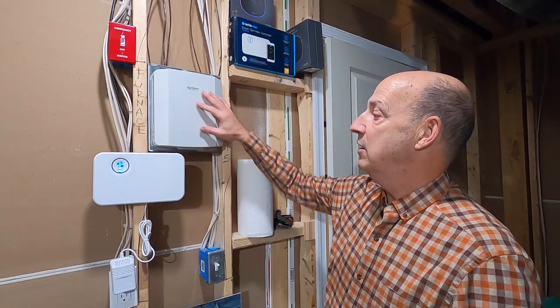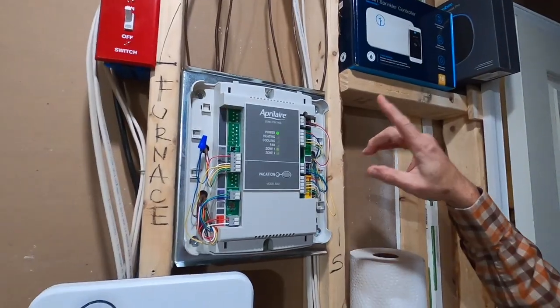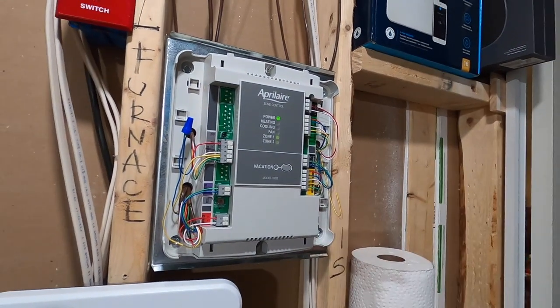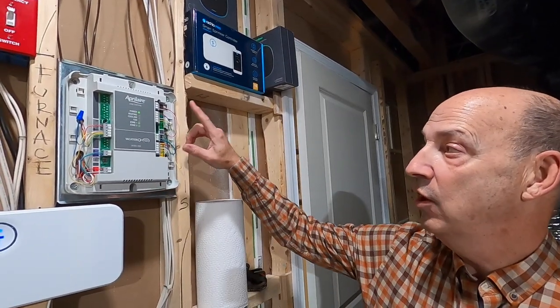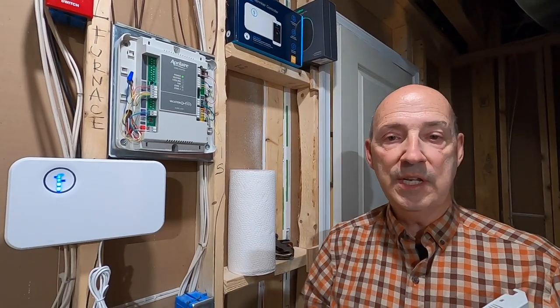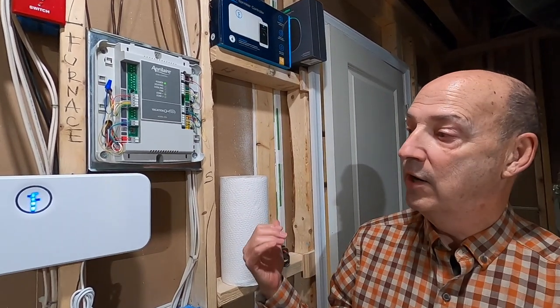In this house we have two zones: your first floor and your upper floors. The basement is tied to that first floor, and it goes to a zoning panel. We have a zoning panel here that gathers feedback from the thermostat up in the living room to the thermostat up in the master bedroom. So when we call for heat on the first floor, we're actually heating the basement — but through controlling the dampers, adjusting the dampers. We've closed a lot of the dampers off upstairs on the first floor so we can get more air downstairs.